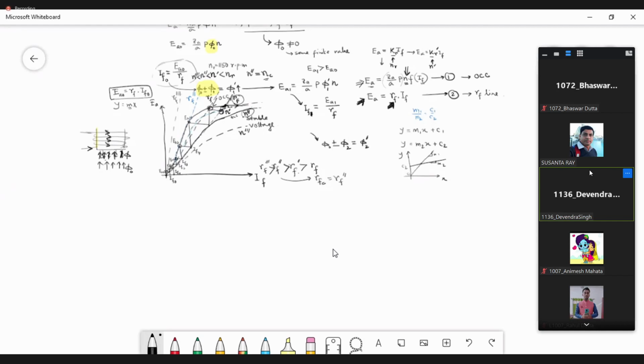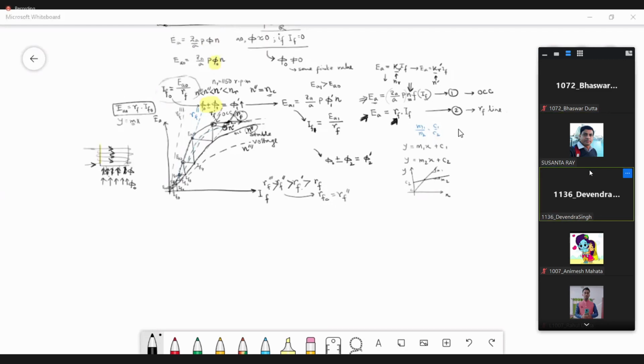The field resistance value should be less than the critical value, and speed of prime mover should be greater than the critical value. And there must be a residual flux to begin the process. And fourth, the field connection should be proper so that the additional flux generated each time gets added to the residual flux so that we can build up. Who is saying this? Sir, Devendra Singh. Okay.